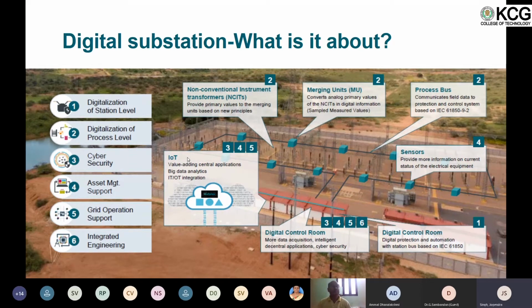During 2000 to 2007-2008, I was at Power Grid India. That's when we started automation, working towards digital substations. The first step was to remove the mimic board and install substation automation systems and substation control. So there are two stages here: the very older type of things, and then the stage where we install substation controllers with IEC 61850.